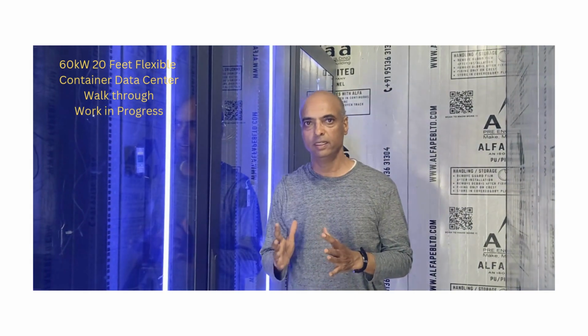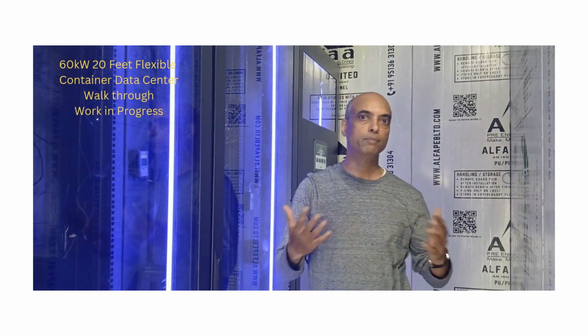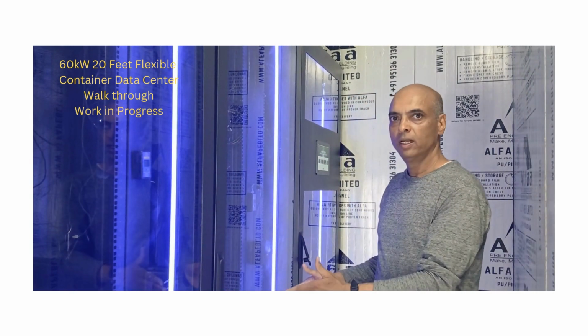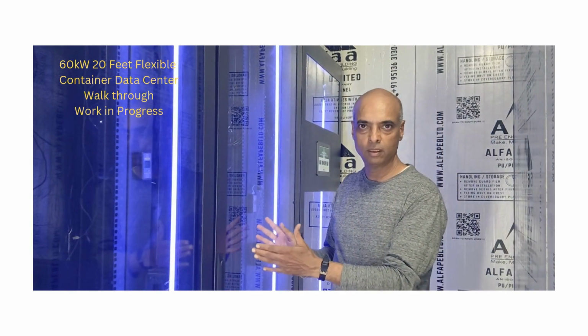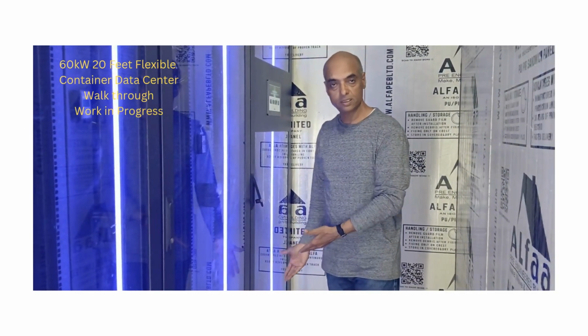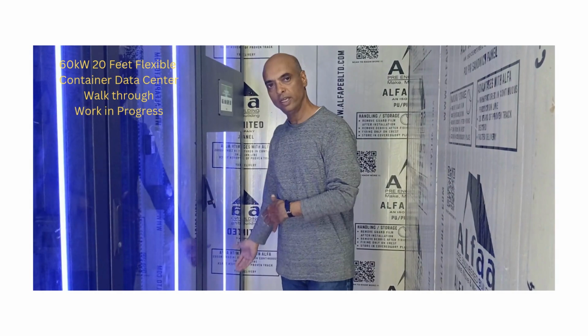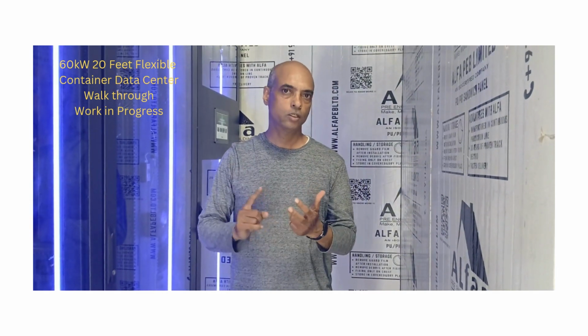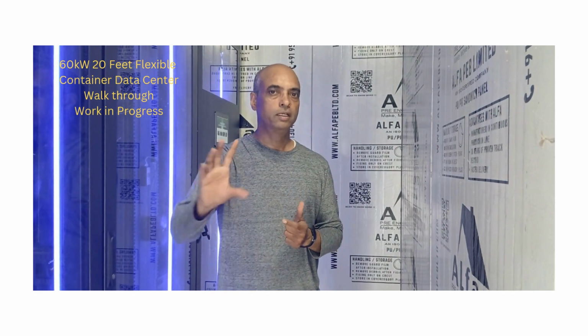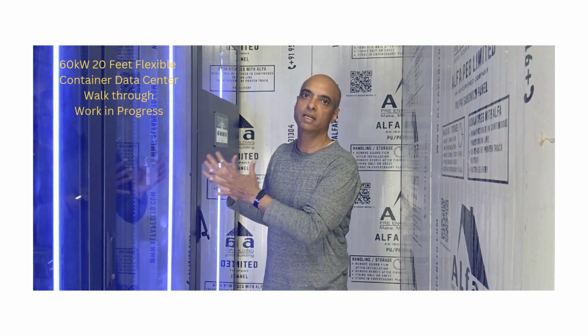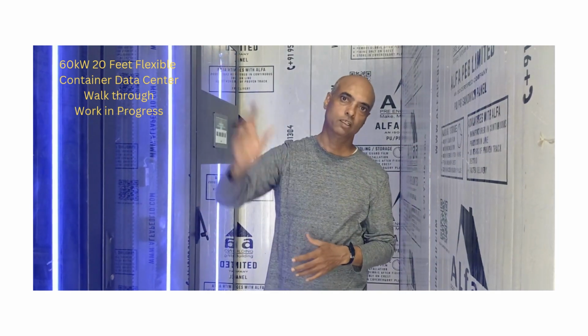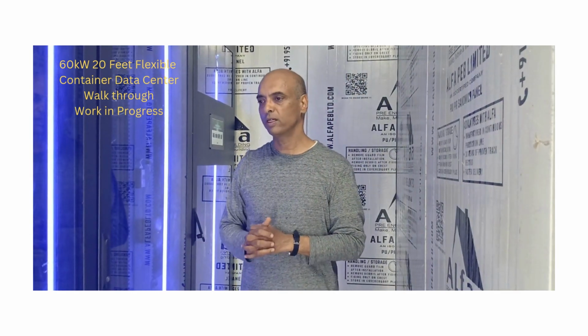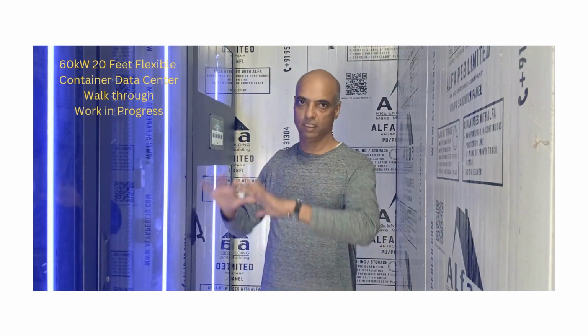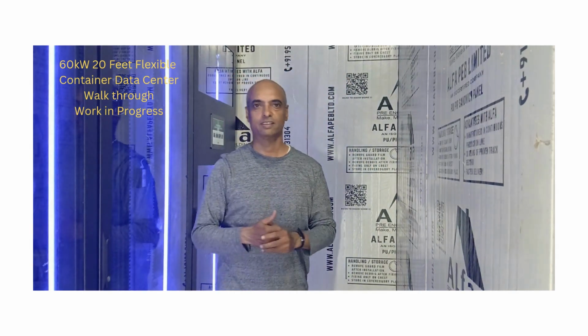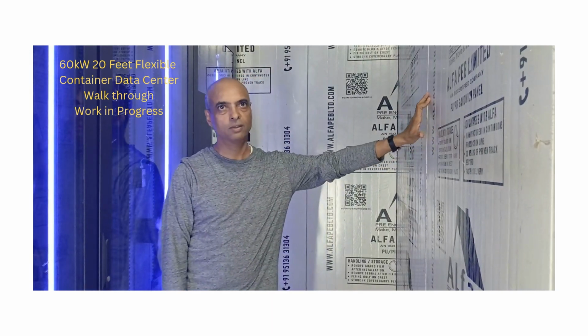The EMS solution has lots of other premium features. We have an in-row air cooling system based on Modbus protocol, and also a UPS system which is also Modbus protocol-based. All this in-rack, UPS, and in-row air cooling system data can be read by our EMS and customized for the customer's requirements. This is one of the very important features we've packaged into the complete data center solution, and most importantly, this is still work in progress.